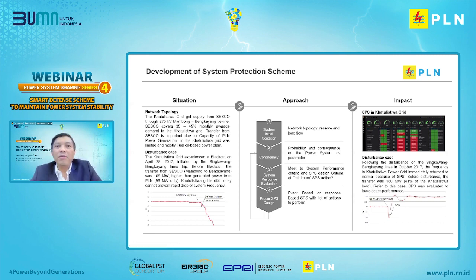Following the same event in October 2017, with the same trips in Singkawang-Bengkayang, SPS could quickly return the system frequency to normal condition through precise load shedding, following the power transfer through the line before the disturbance. So we can see on the chart on the right, after we installed SPS, the system can recover back to normal immediately because the SPS can shed the amount of megawatt or number of feeders that matches the power loss from the transfer.